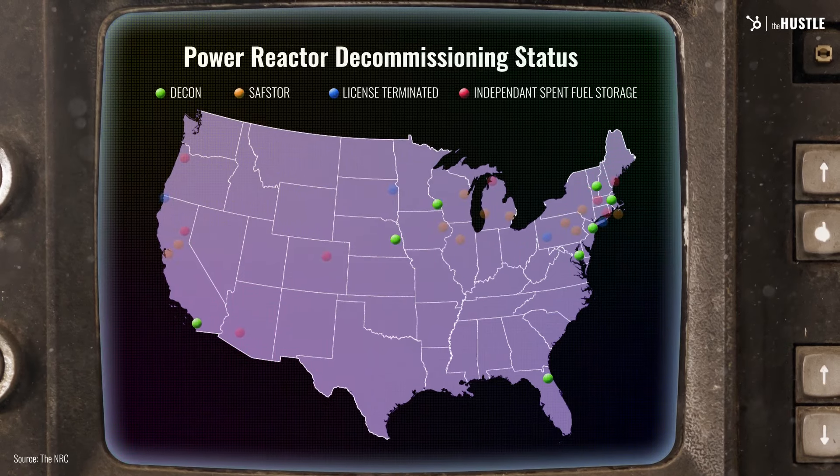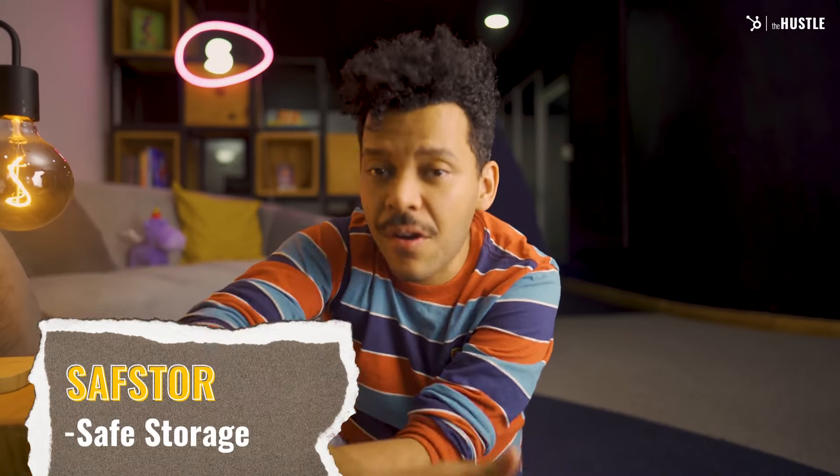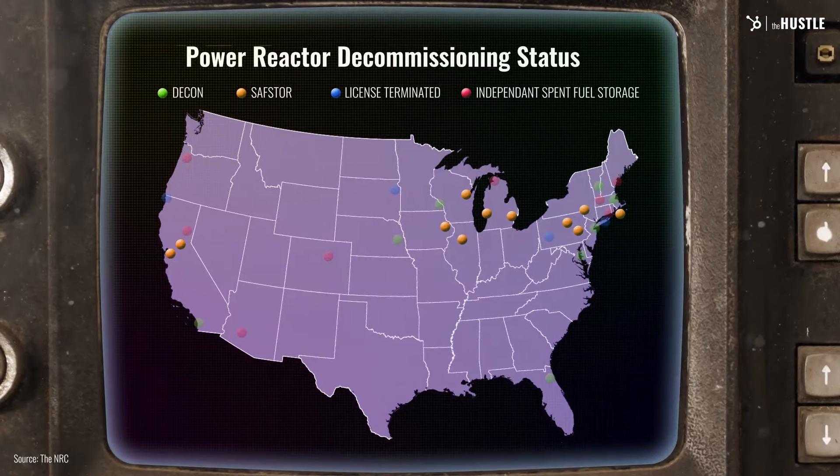Did they have to reopen this plant in particular? Three Mile Island was actually ready for decommissioning — was there no other choice? Not really. Only a handful of plants in the US fit the criteria for reactivation. When a nuclear power plant reaches the end of its lifetime, the company can choose one of two paths. The DECON path — decontamination and immediate dismantling — means equipment and structures containing radioactive contaminants are removed or decontaminated shortly after the plant ceases operation, releasing the site for unrestricted use. The other path is SAFSTOR, or safe storage, where the facility is maintained and monitored while radioactive materials decay for up to 60 years.